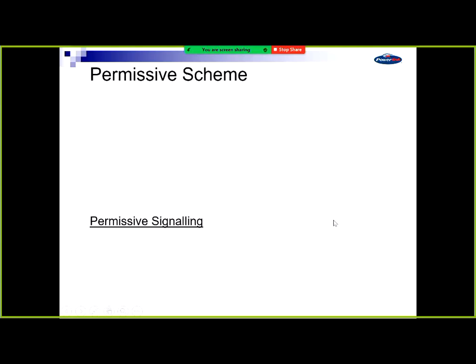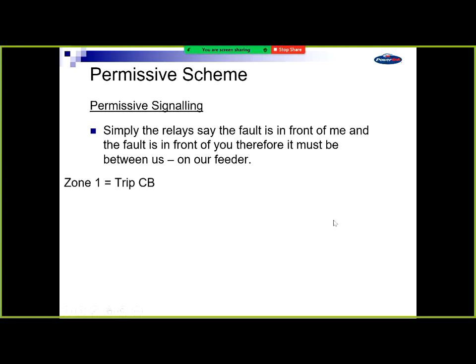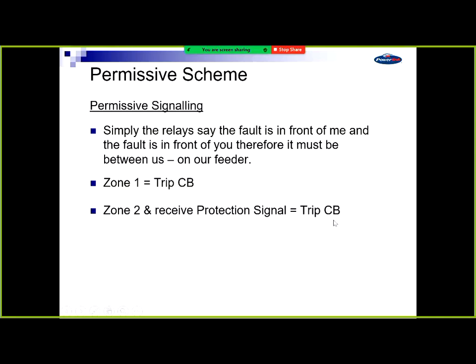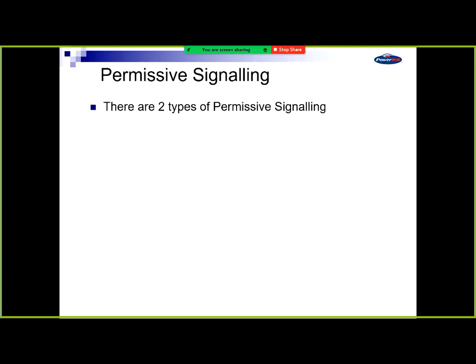Our 2 schemes are permissive and blocking. They operate on different philosophies. So zone 1 is always a trip the circuit breaker. The zone 2 is, I've got a zone 2 and I receive a permissive intertrip from you, I trip. A zone 2 plus our zone 2 time delay, we always trip. So protection signalling doesn't stop the relay from going in a slow zone 2. It basically just speeds up that slow zone 2 for a fault on there.